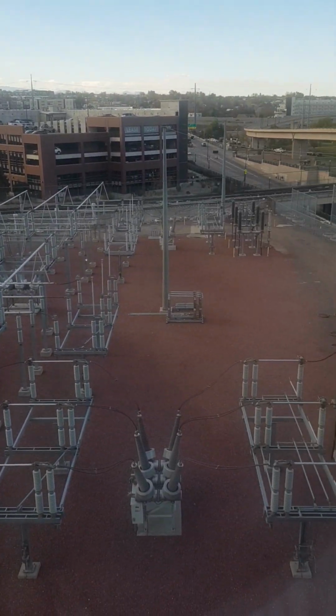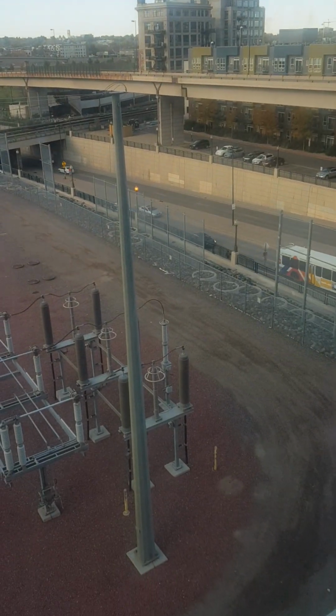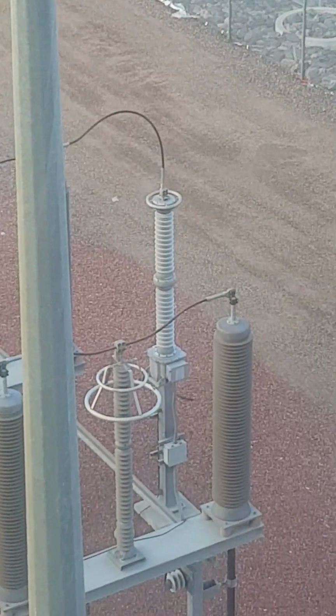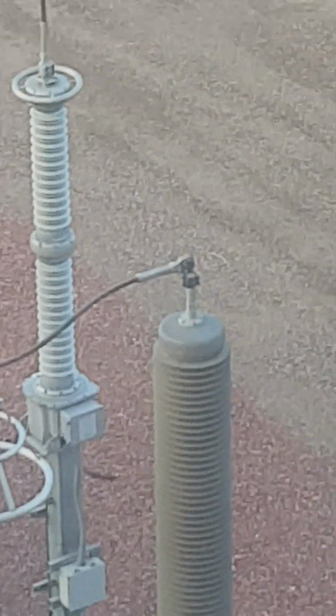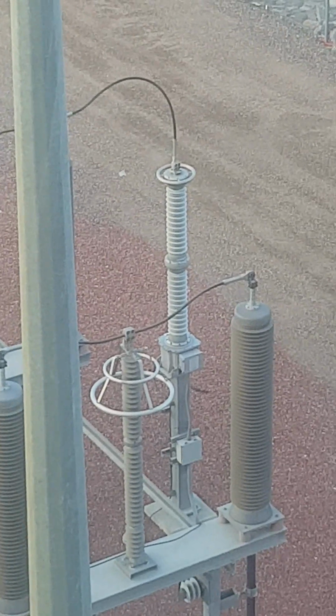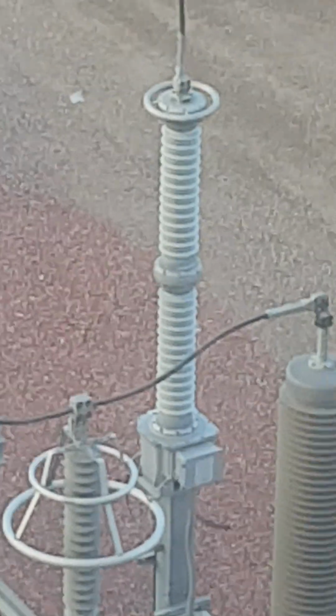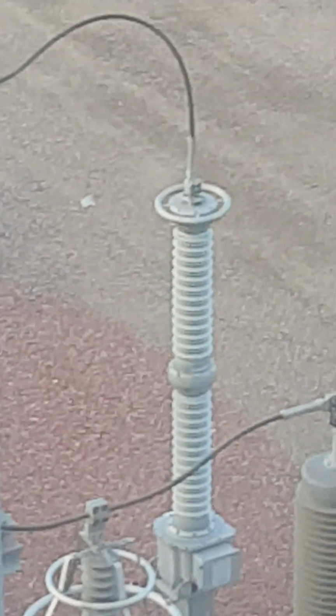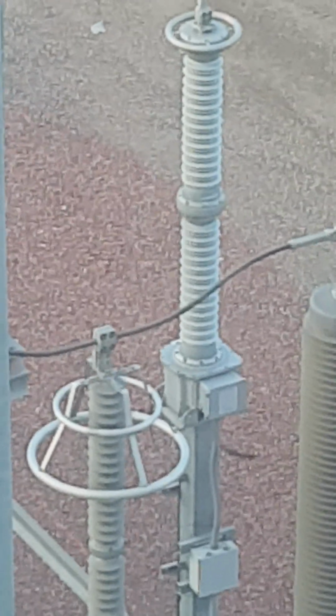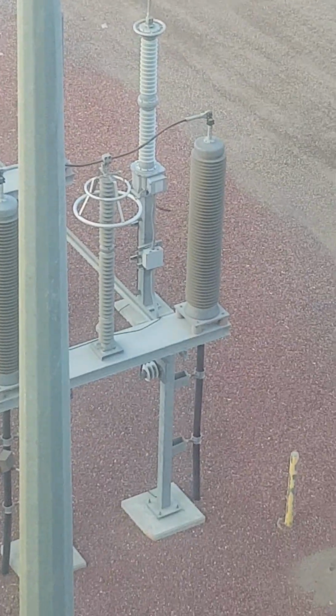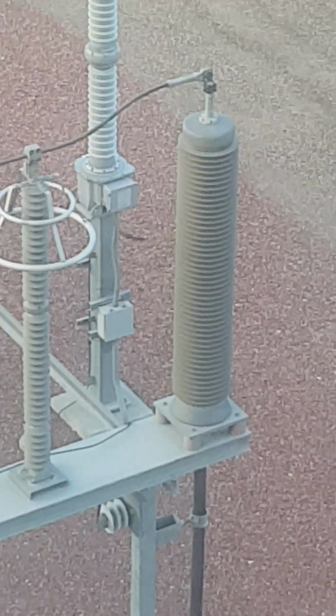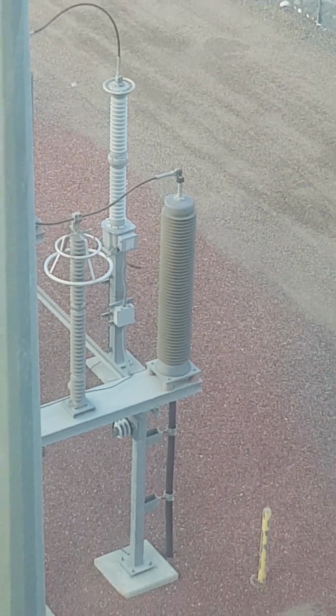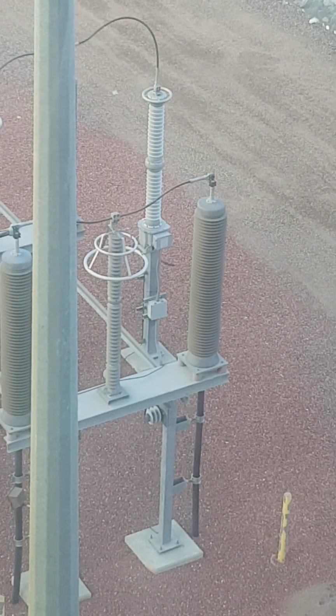So let me take you and try to explain the different components of that substation as we start from the beginning here. At the beginning, you need to measure the voltage and the current. And to measure the voltage, we use what we call the CVT, capacitive voltage transformer. This is the CVT. So it's basically two things in one. It's a capacitive divider that reduces the voltage to a certain level, and then there is a transformer that steps down the voltage further so that it can be measured inside the substation. Also, we have the current transformers. These current transformers are basically used to measure the current. So it steps down the current to a safe level so that it can be measured inside the substation.